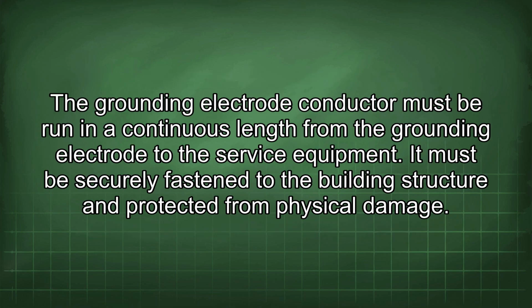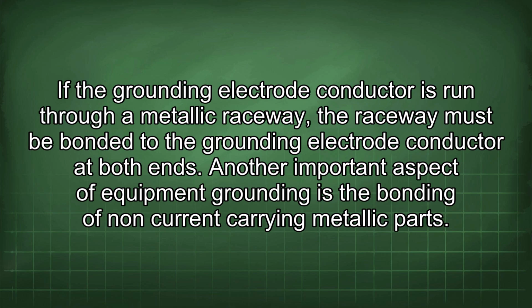The grounding electrode conductor must be run in a continuous length from the grounding electrode to the service equipment. It must be securely fastened to the building structure and protected from physical damage. If the grounding electrode conductor is run through a metallic raceway, the raceway must be bonded to the grounding electrode conductor at both ends. Another important aspect of equipment grounding is the bonding of non-current carrying metallic parts.